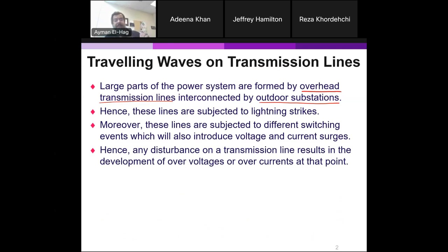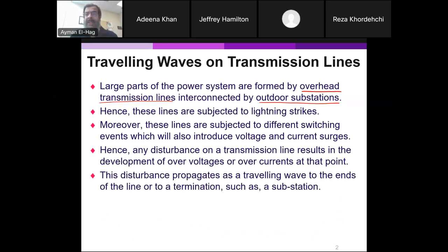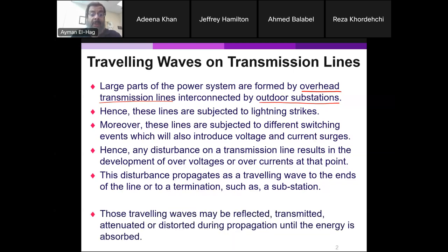Now, when a disturbance happens from a lightning event or from a switching event, this will lead to an overvoltage or an overcurrent at that specific point. It's not that the problem only happens at that specific point, but these surges will propagate in the system until they reach a termination, like for example a substation, and we will see what happens as those surges travel in the transmission lines.